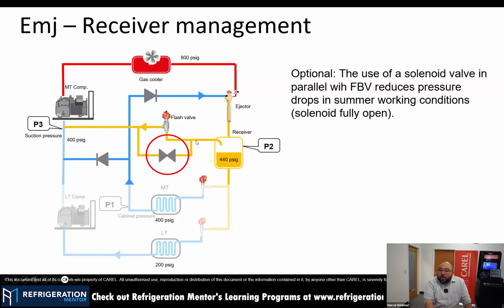So what you can do, CAREL has an internal logic that we can activate: a parallel solenoid valve bypassing the bypass valve. So we have here a valve that's bigger than our bypass valve and would reduce the pressure drop through this valve to almost zero, or very close to zero. And this valve is activated when the flash gas bypass valve is open for a certain percentage for a certain time, so we make sure that at that point during summer we really need all the gas passing through these valves, reducing the pressure and increasing the pressure here at the liquid receiver. So this would make our system even more efficient because we are not expanding to compress again, we are just compressing directly from the liquid receiver.